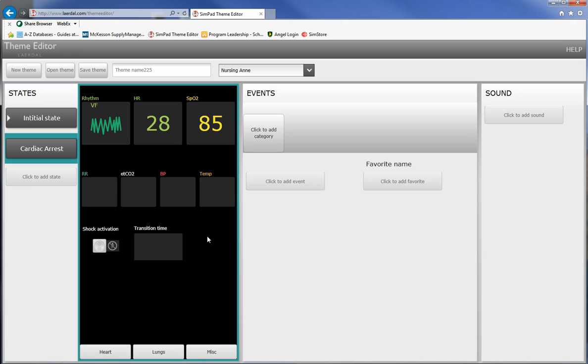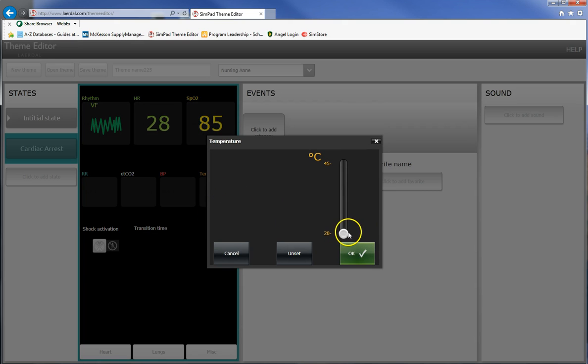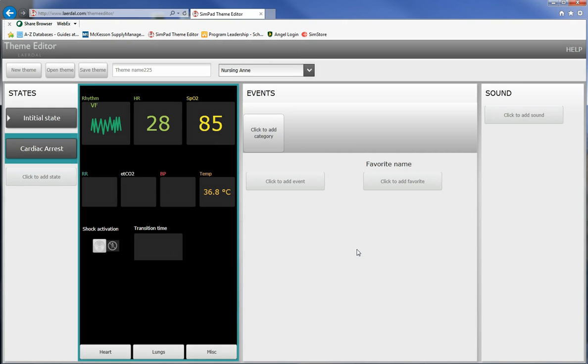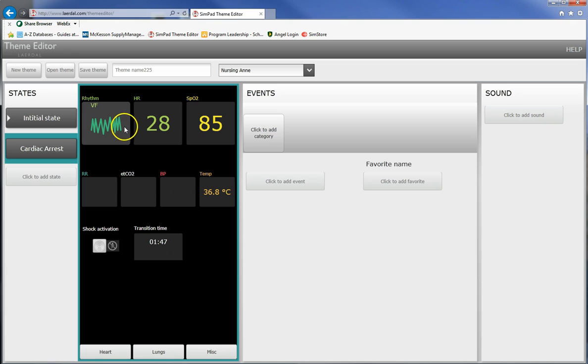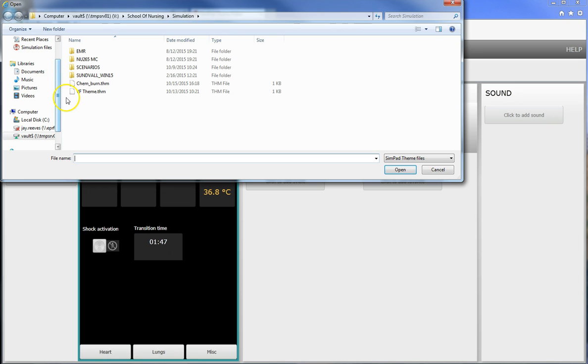Blood pressure should be zero and one of the reasons why it's not showing up here is because there's V-fib. The mannequin knows that once V-fib occurs it needs to stop breathing, it needs to stop its blood pressure. The blood pressure is going to fall out. Temperature on the other hand we could still maintain and depending on how complex you want to be you could set temperatures and then talk about things like post-arrest hypothermia. From here I'm going to stop this recording of how to set up states in SimPad theme editor and I'm going to switch over to a different theme that already exists so I can show you more about this section over here, events.